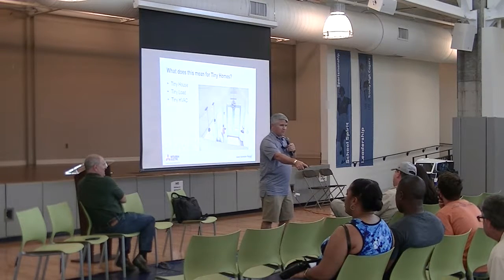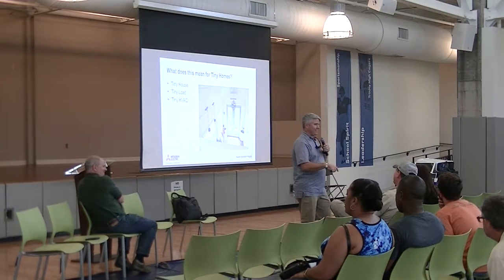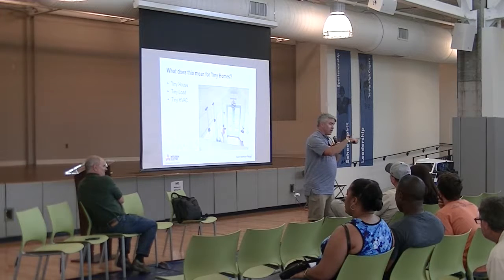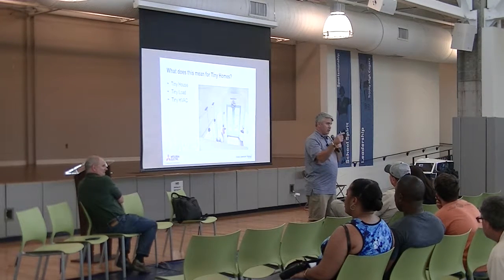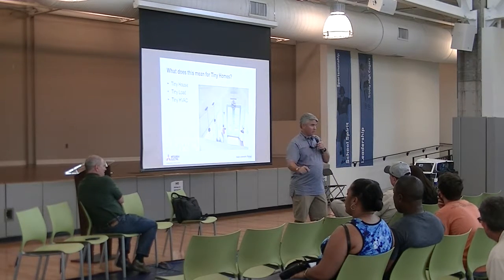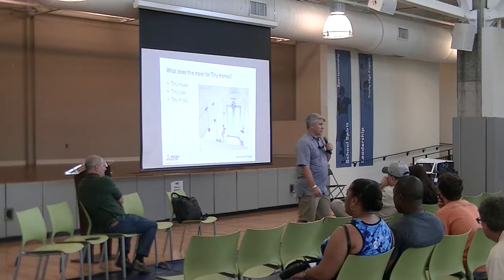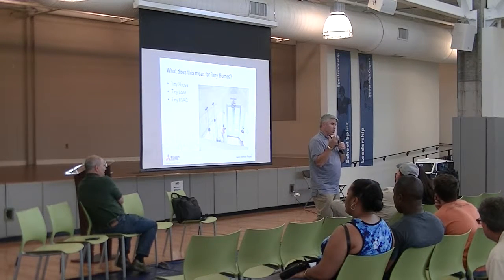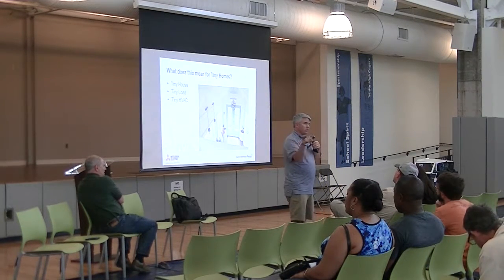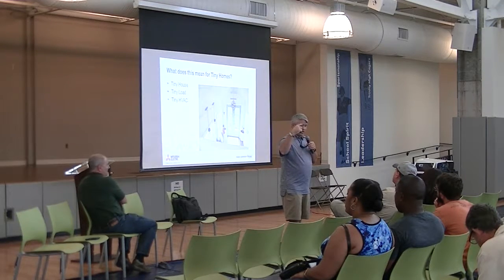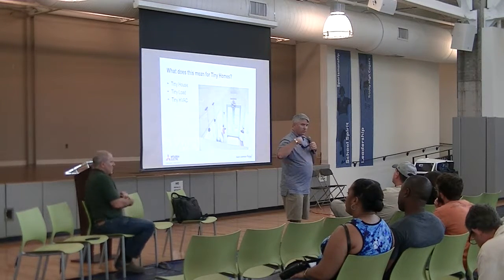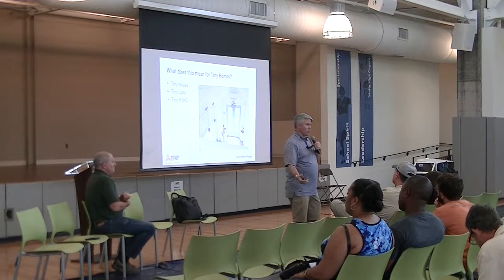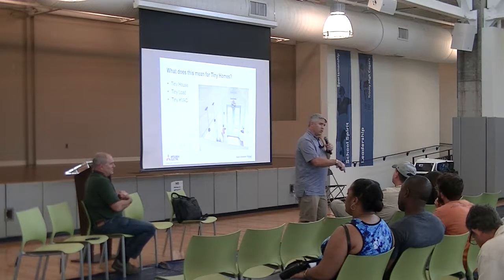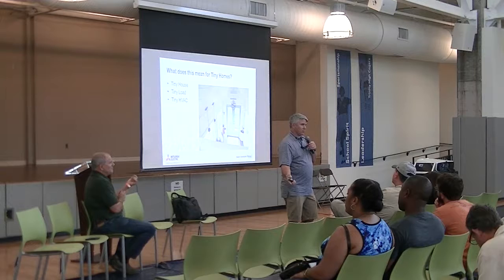We have to run air across a cold coil. When that happens, the air reaches dew point, condensation occurs, and that's why there's a drain to the outside from air conditioning—we literally wring the moisture out of the air by running it across a cold coil. We have to do that over a certain period of time before we begin to remove any moisture, and if you cool the space too quickly, you don't get enough run time to do that.